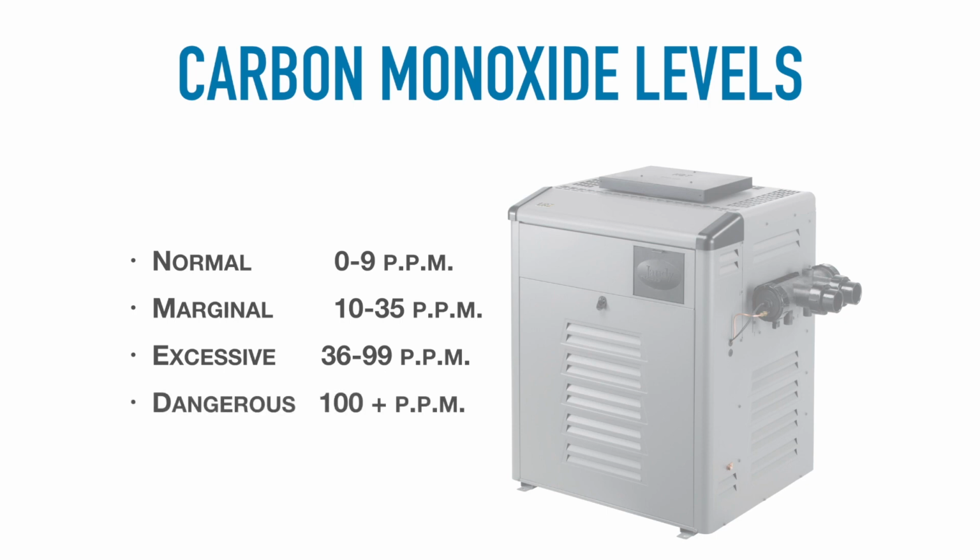Make sure that you're using a system that can actually be tweaked and set as far as the parameters go, to go off between 36 and 99 parts per million once it detects those. So again, make sure that we have these professionally installed so that venting hood is properly venting all of that carbon monoxide away from you and your guests.